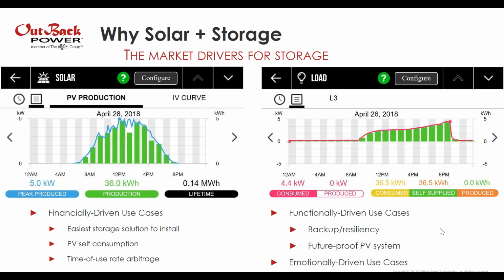And you can see that from the pictures here up above. These are actual screenshots from a SkyBox system. And what we're seeing here with this particular SkyBox is 5 kW PV production during the day, peaking at noontime. And that doesn't match up with the household load, which is presented on the right-hand side. So how is it that this particular SkyBox is able to do 100% self-consumption? Well, it's doing that by charging the battery while it's simultaneously powering loads during the day and then discharging that battery in the evening when the sun's gone down.